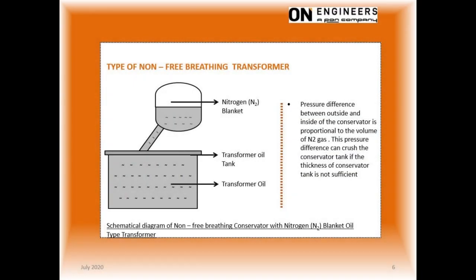This slide shows yet another variant of the non-breathing transformer. The headspace is created in the conservator tank. The headspace is to accommodate the thermal expansion of the oil when the transformer is loaded up. There will be a limit to the size of the transformer for such a design.